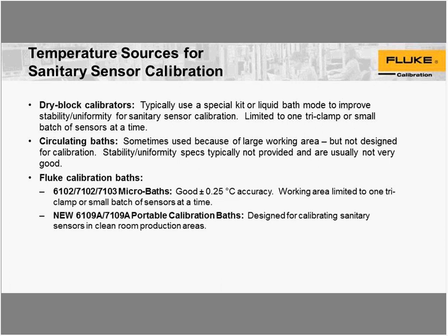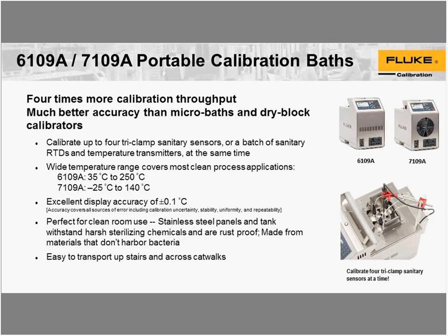The other category is the new 6109A and 7109A portable calibration baths that are designed specifically for calibrating sanitary sensors, so they have a larger tank, and they're also set up better for use in a clean room. So let's talk about that a little bit more here. I think we'll refer to these as tri-clamp calibration baths, maybe for the rest of the webinar.